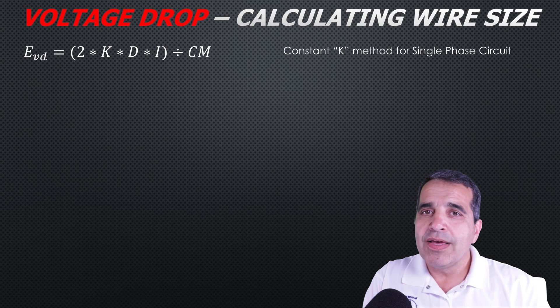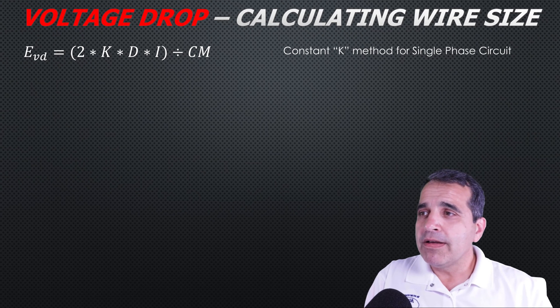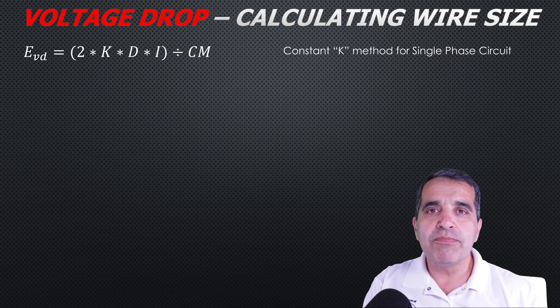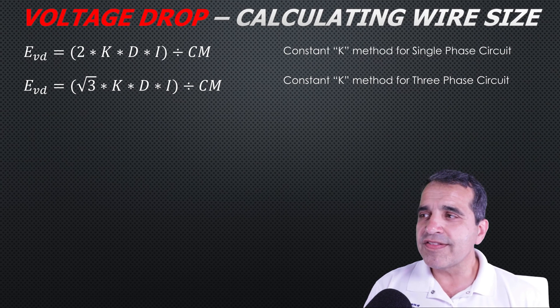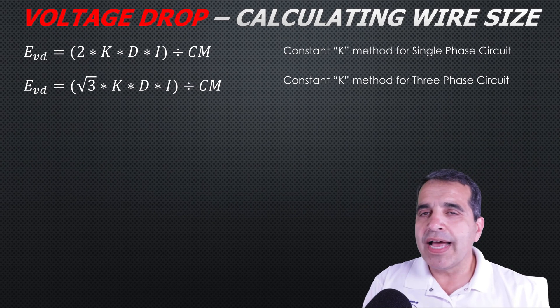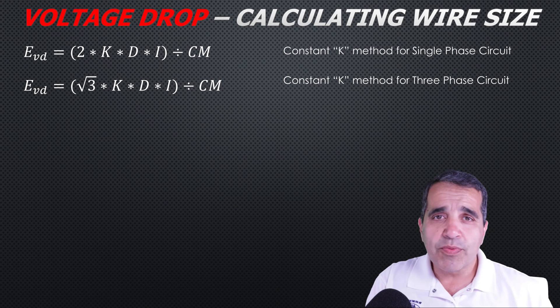If you have a 20-amp branch circuit, the maximum continuous load would be 16 amps, and you can plug that in as the amperage. Then divide by the circular mils of the conductor to get the voltage drop. For three-phase loads, everything is the same except the two is replaced by the square root of three, which is 1.732 — because you have three conductors feeding a three-phase circuit.